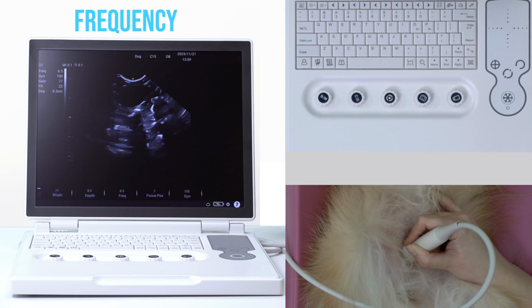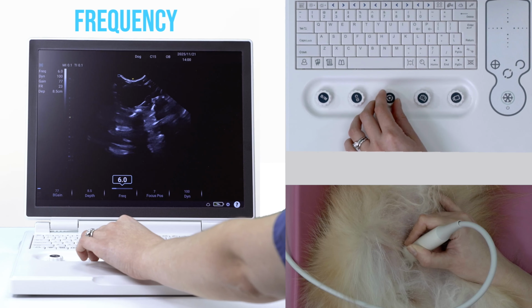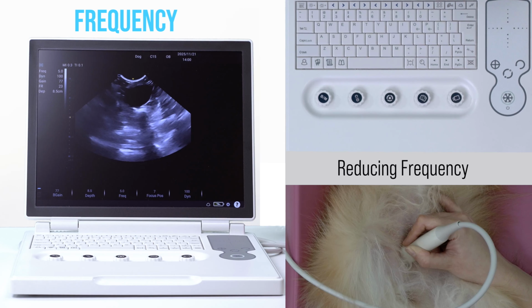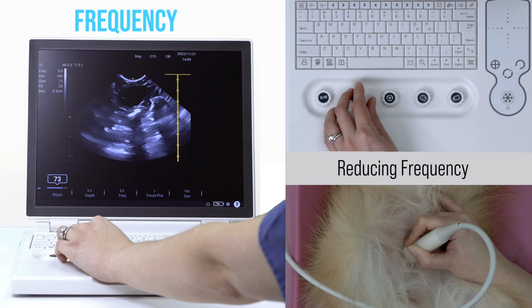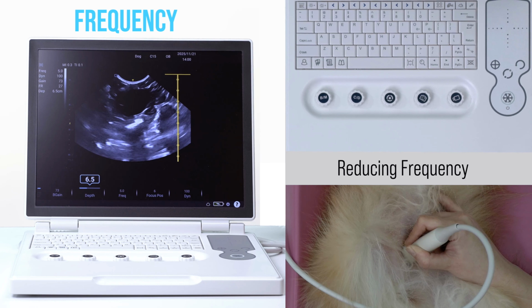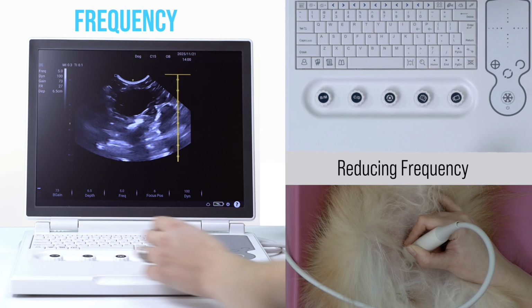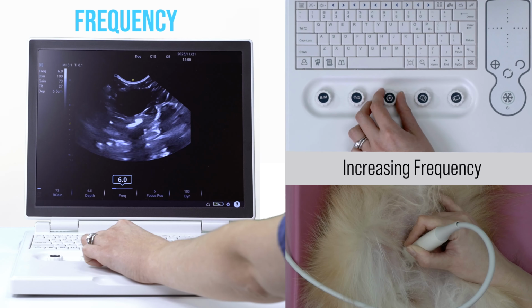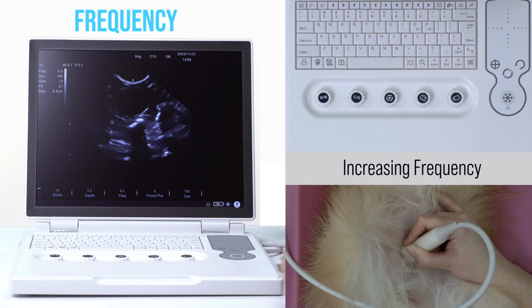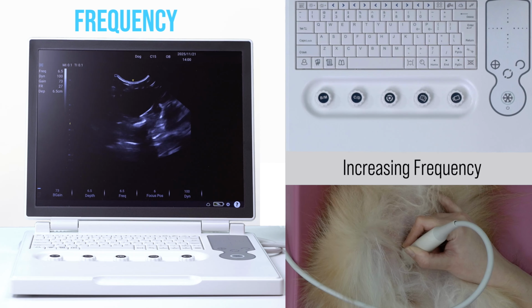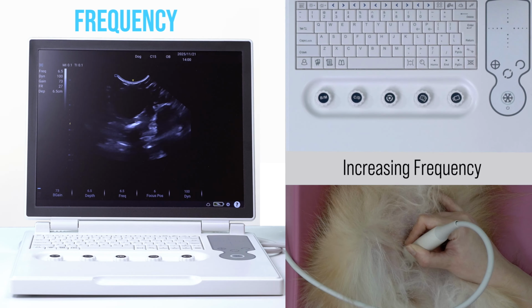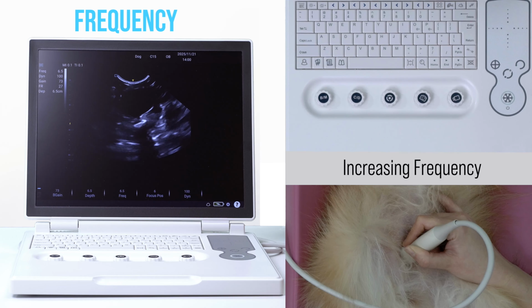With frequency, you'll often leave it on its default setting, but if you find an animal to be particularly difficult to scan, maybe they're particularly large or overweight, you can reduce your frequency and that will give you better penetration, but it will slightly reduce your image quality. Conversely, you can increase your frequency to get much higher quality, but you will not have as much penetration. So that's fine on a small dog like this, but might not work on a larger animal.